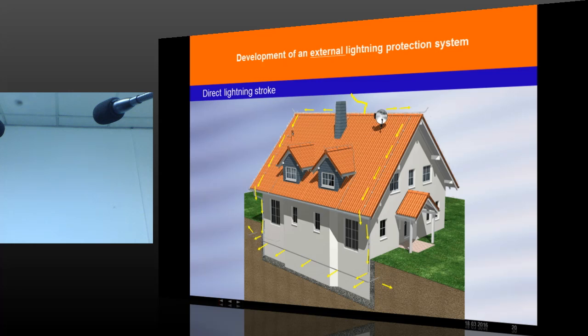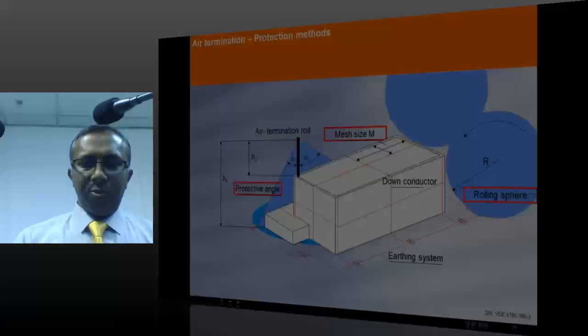And in this particular case, a direct lightning strike on a building, it is calculated in the standard that approximately 50% of the current goes to earth and 50% gets into the building. So 50% of the current can flow inside the building. Under what conditions is explained.